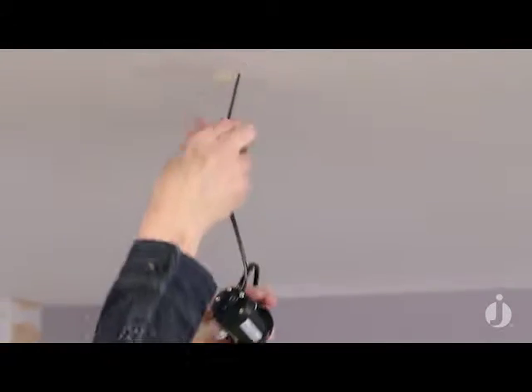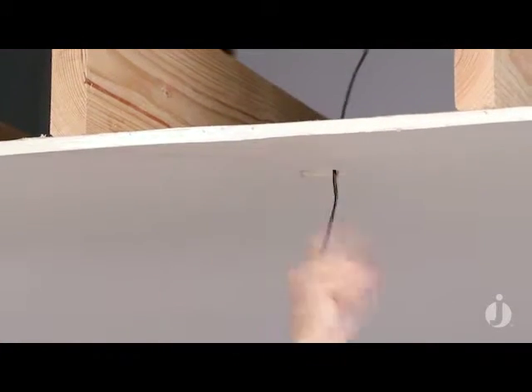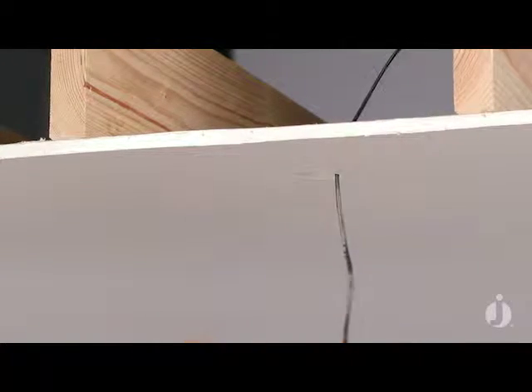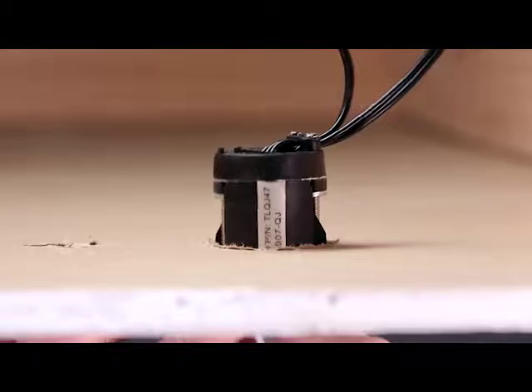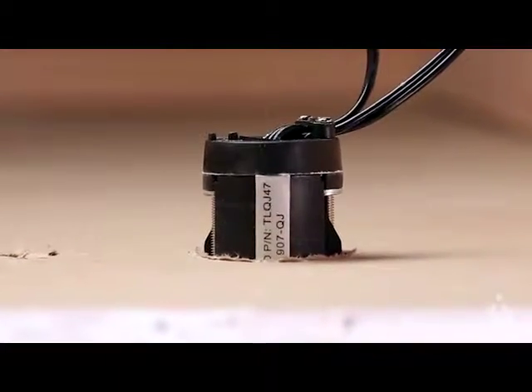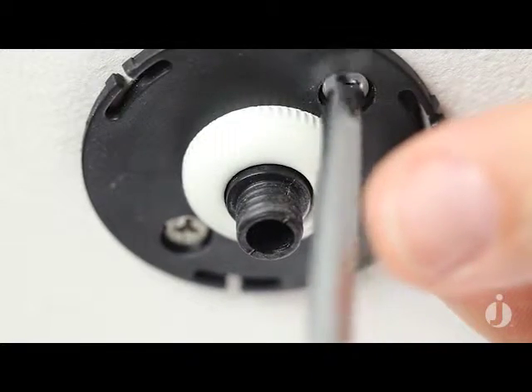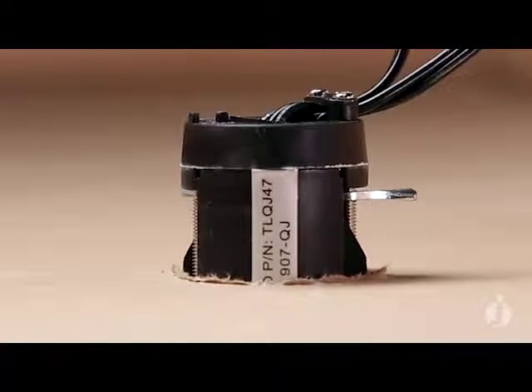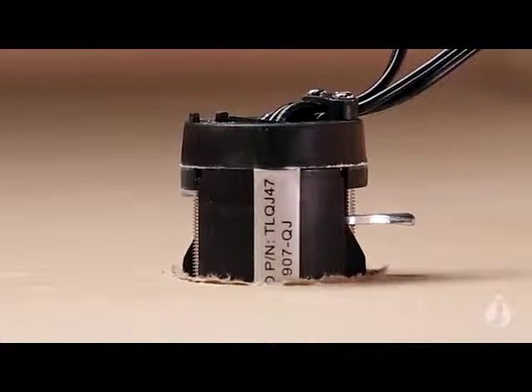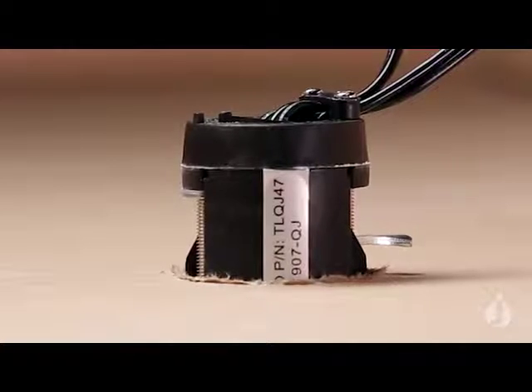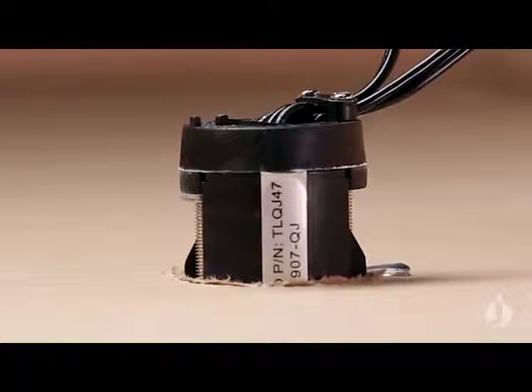Here's my lead coming from my first fixture, and here is my lead going to my next fixture, which I'll push up through the hole. We're going to tighten up those two screws that bring those wings down, sandwiching the drywall between the wings and the flange on the bottom of the plate.